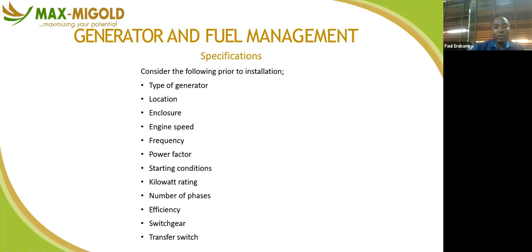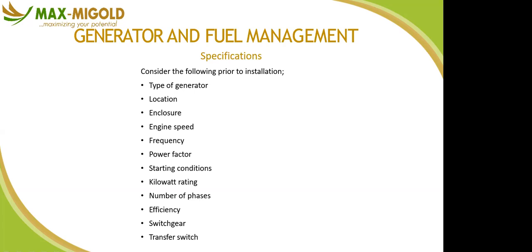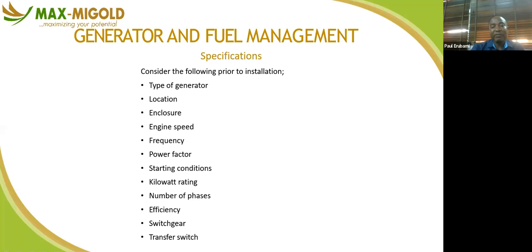So when you want to install, you consider all these things: location, enclosure. That's what they call site inspection. You come for site inspection to know where to position your generator, the engine speed, and so on. The engine speed should not be more than about 1,490 or 1,500, so the range is 1,500 revolutions per minute. So you know all those things: engine speed, frequency, power factor. Our power factor here in Nigeria is 0.8.